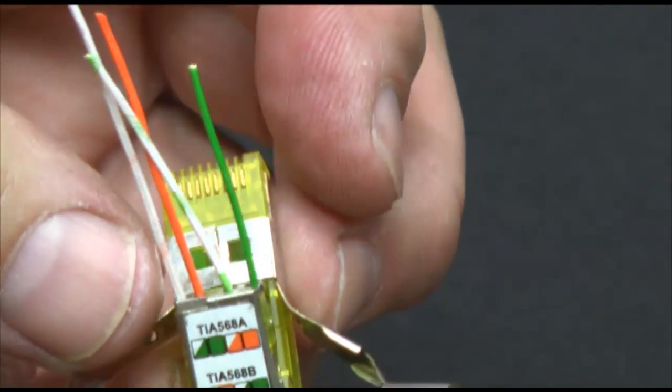Slide the connector back as far as it will go towards the foil tape. Then using your snips, cut off the excess conductors as close as possible to the connector door. Then firmly press the small door closed to complete your IDC connection.